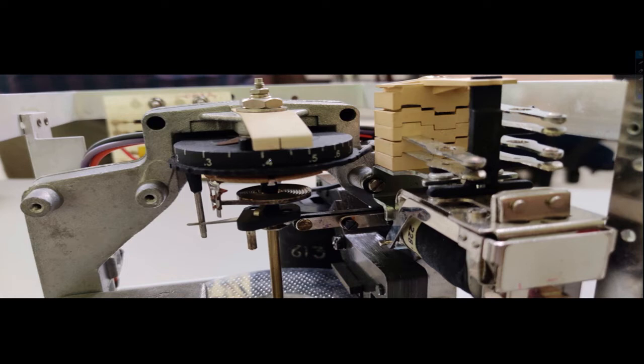And also sometimes the relay can be operated instantaneously, meaning as soon as the current goes beyond the set value of the current for the relay, it will instantly generate a trip signal. So based on the application, based on where you want to install the protection, and based on the apparatus you want to protect, sometimes the relay operates instantly, sometimes purposeful delays are there. So this delay can be set here. So how to set the delay?